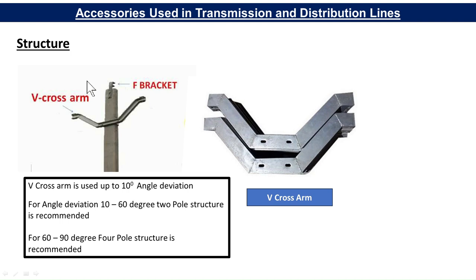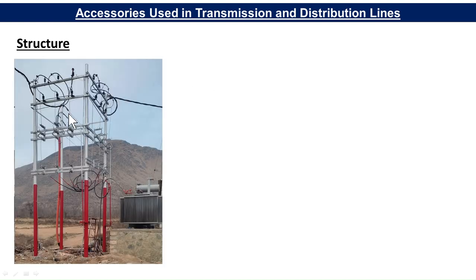Now looking at distribution structure types: V cross arms and F brackets are used for distribution. V cross arms are used up to 10-degree angle deviation of the line. For angle deviation from 10 to 60 degrees, a two-pole structure is recommended. For 60 to 90 degrees, a four-pole structure is recommended — four poles at four corners are used. Here you can see the line coming from one side and going at a 90-degree angle deviation.